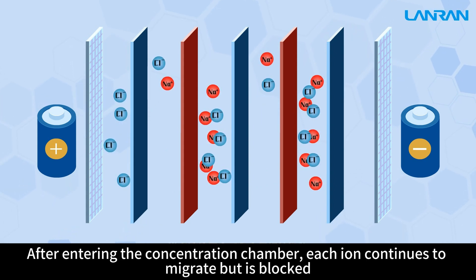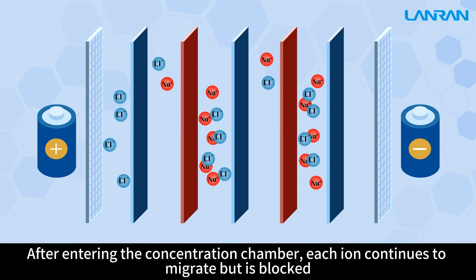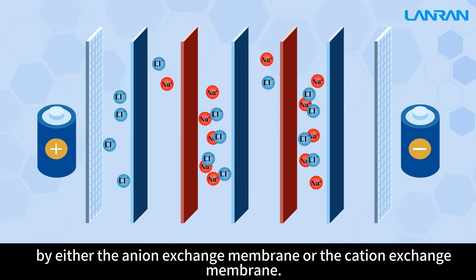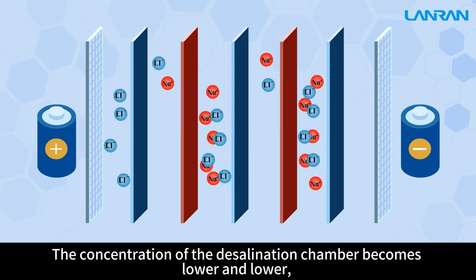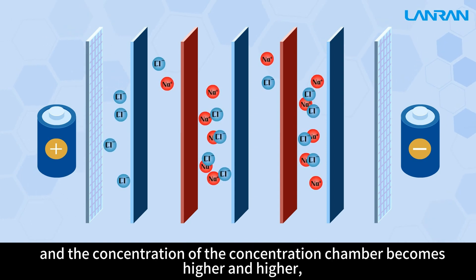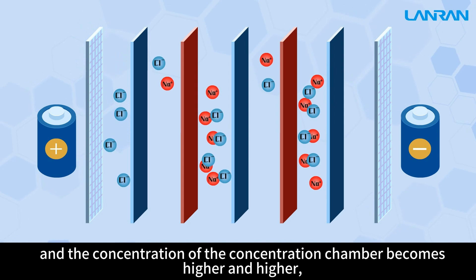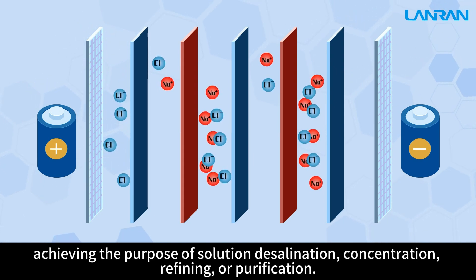After entering the concentration chamber, each ion continues to migrate but is blocked by either the anion exchange membrane or the cation exchange membrane. The concentration of the desalination chamber becomes lower and lower, and the concentration of the concentration chamber becomes higher and higher, achieving the purpose of solution desalination, concentration, refining, or purification.